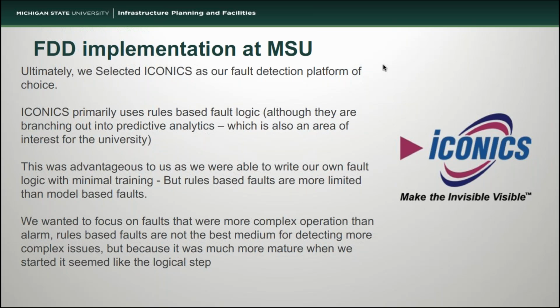The downside of rules-based faults is that they're a lot more limited in functionality than model-based faults because they don't make any future predictions. They simply collect the data, and then you really do most of the interpretation. We did want to focus on faults that were more complex in operation than alarms, and rules-based faults are also not super great for detecting complex issues because they really can't fill in the gaps that a person looking at the system would. But at the time that we were looking in 2013, rules-based fault detection was a lot more mature than model-based fault detection, and so it felt like the most logical step for us to take at the time. Next slide.